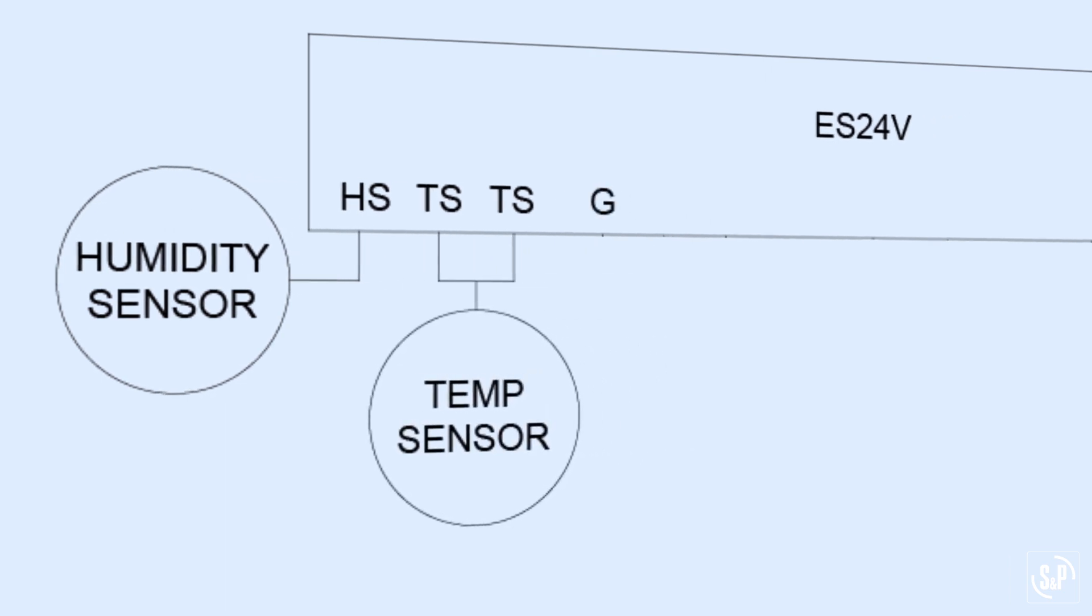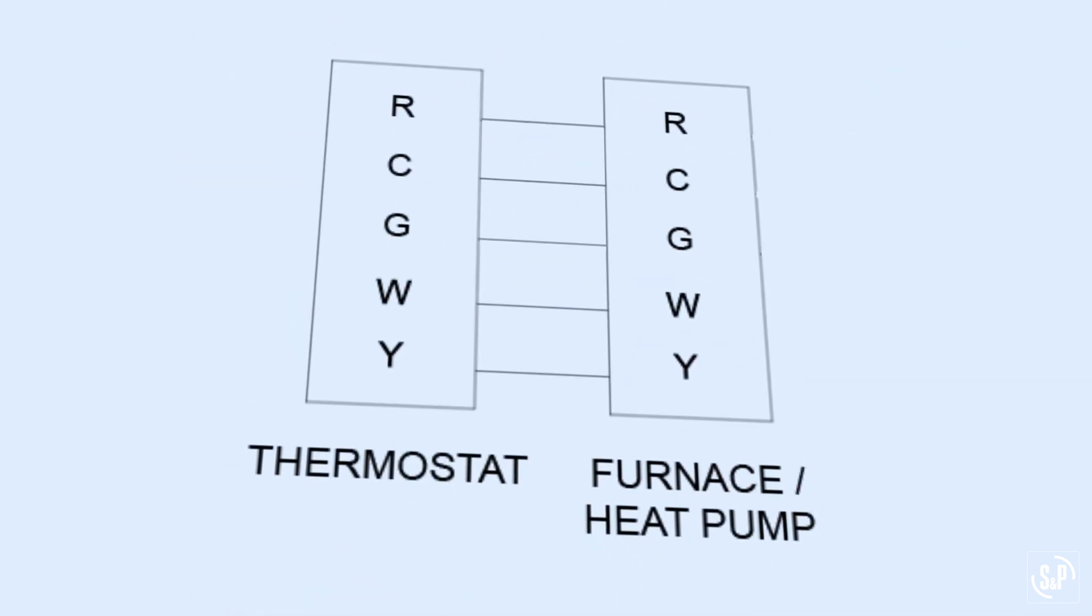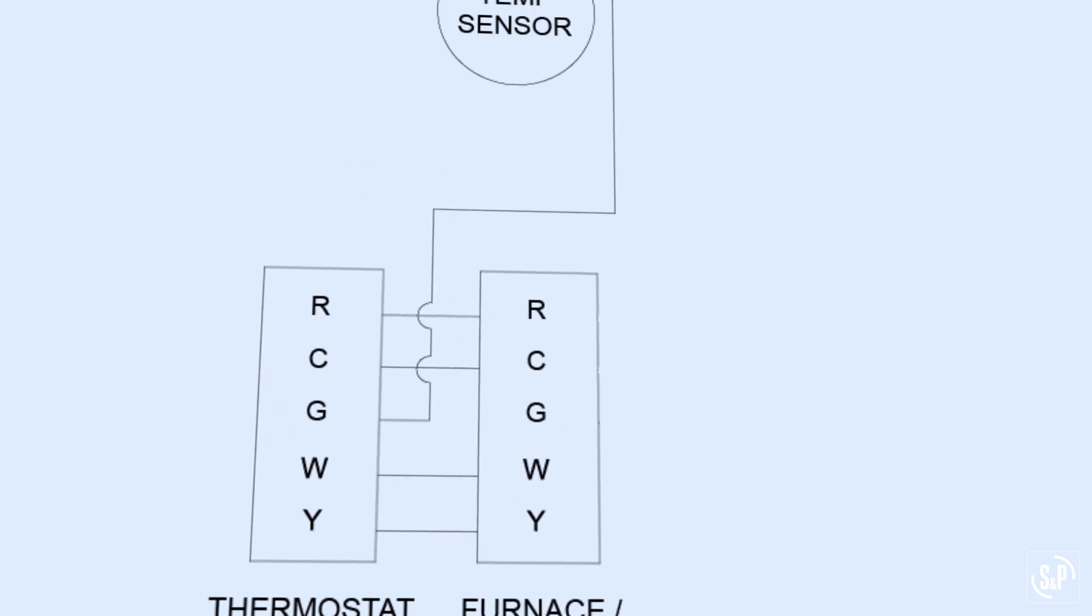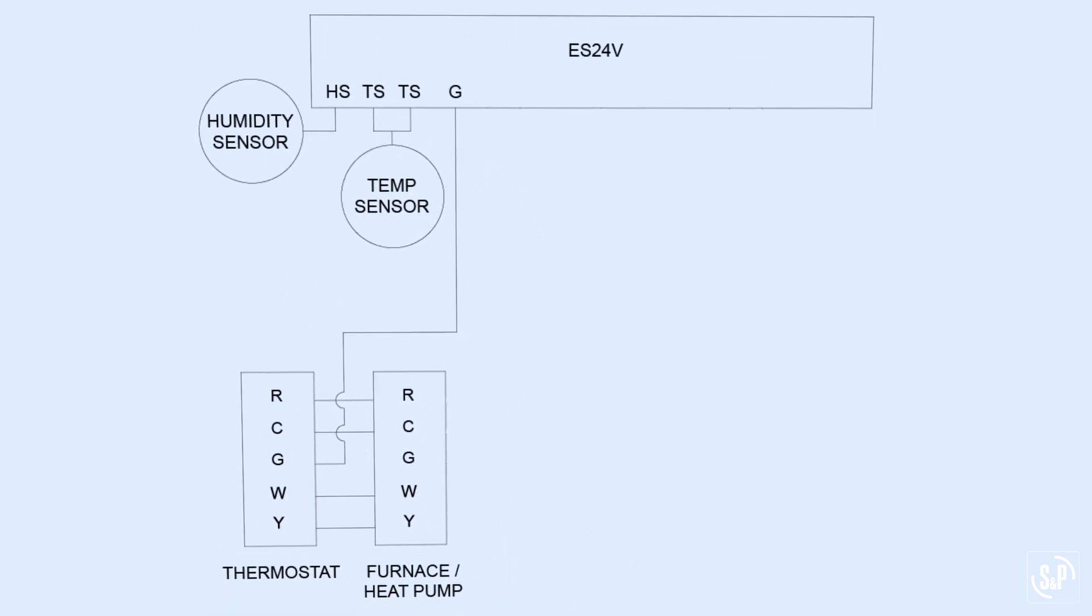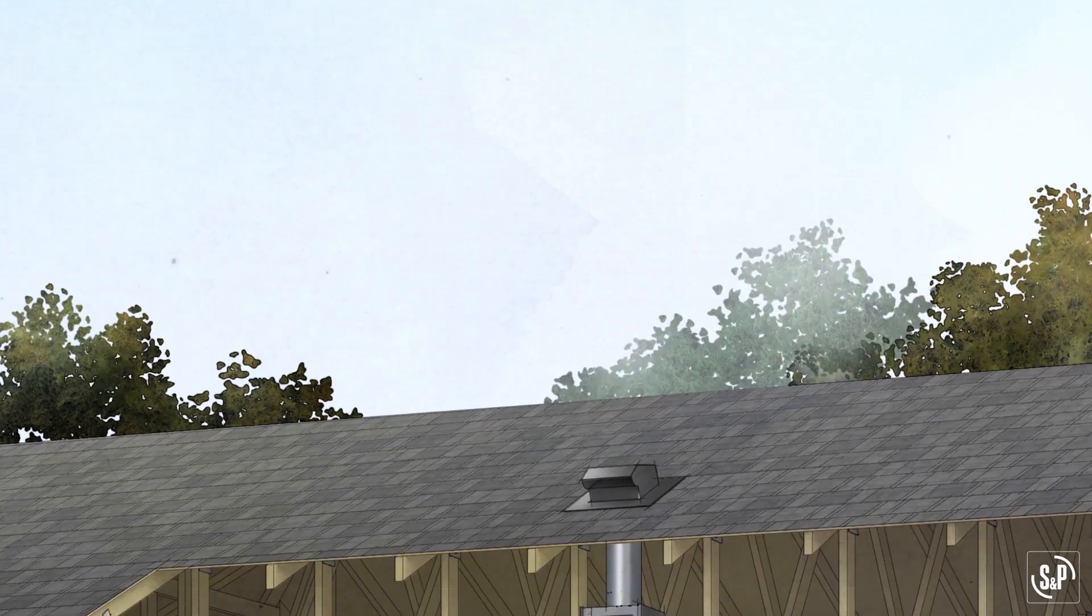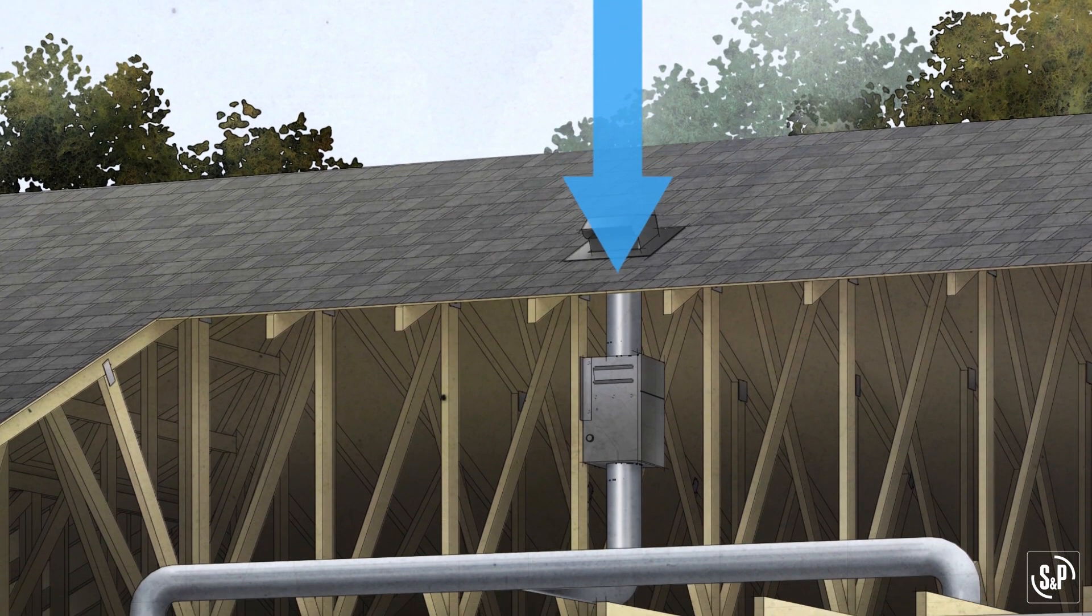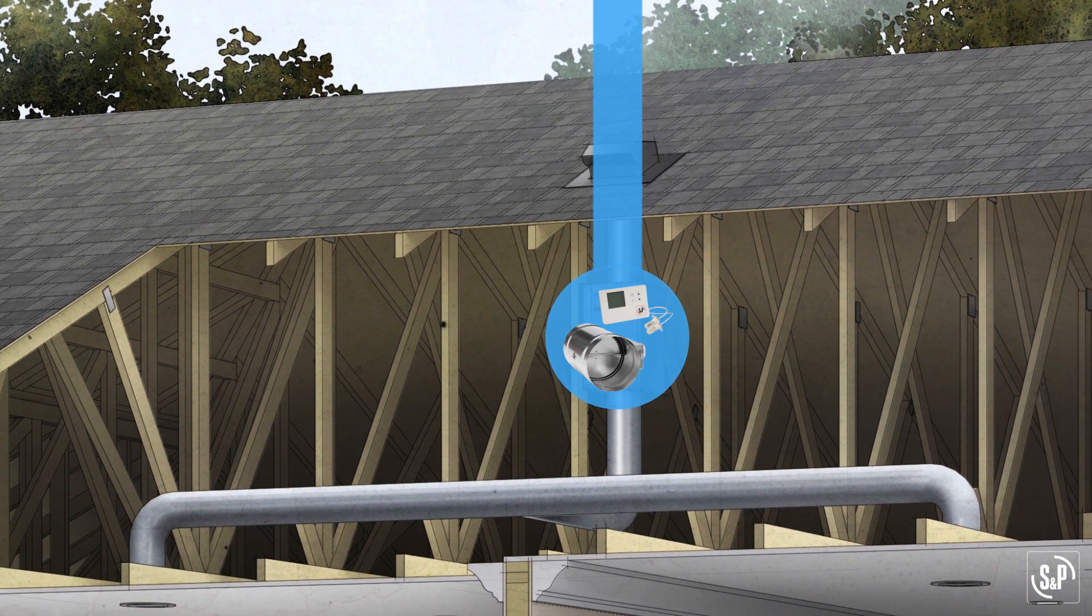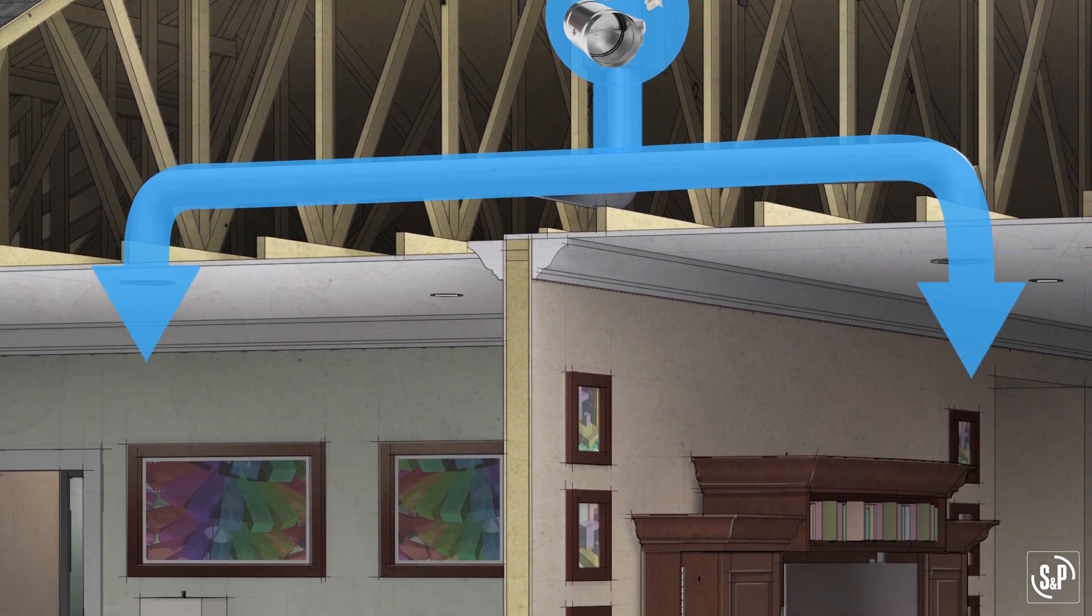The G terminal is the air handler unit input. The G wire that is normally connected from thermostat G to HVAC unit G is disconnected from the HVAC unit and connected to the ES24V G terminal. This is required in central fan integrated fresh air supply systems in which a motorized damper is connected to the HVAC return plenum to pull fresh air in.